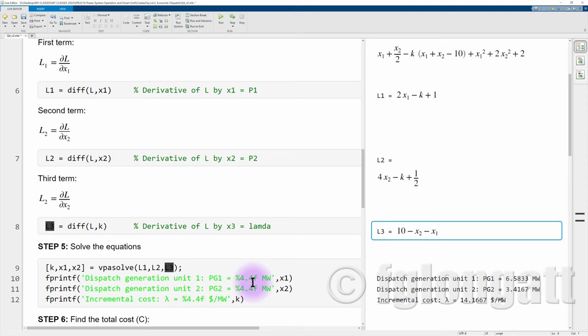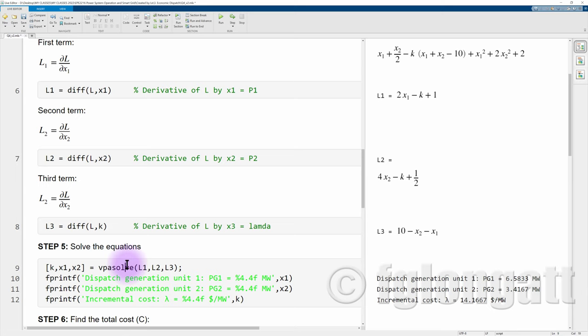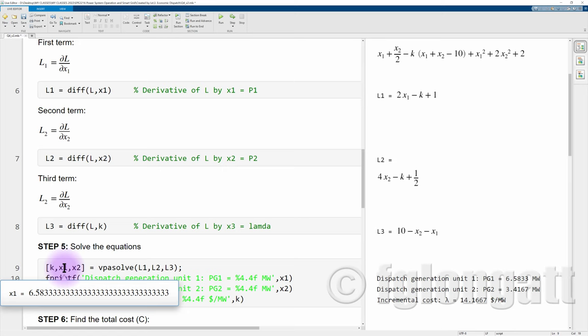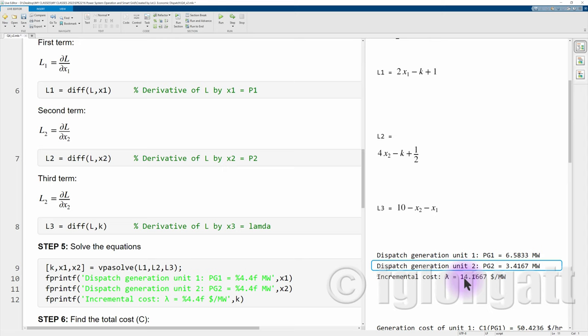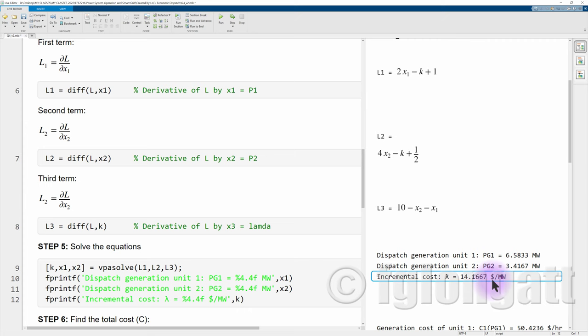Now we use the MATLAB command vpasolve, which solves the set of equations. Solving equations L1, L2, and L3 together, we obtain that the power dispatch of generator one is 6.58 megawatts, the dispatch of generation unit two is 3.41 megawatts — and you can verify that their sum equals 10, the total load. We also obtain the incremental cost, which in this case is 14.16.